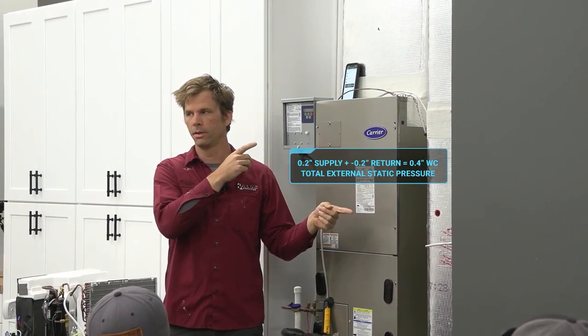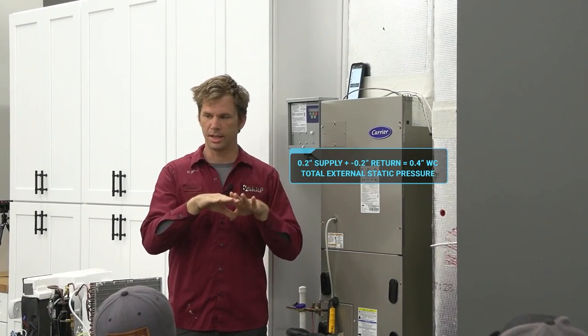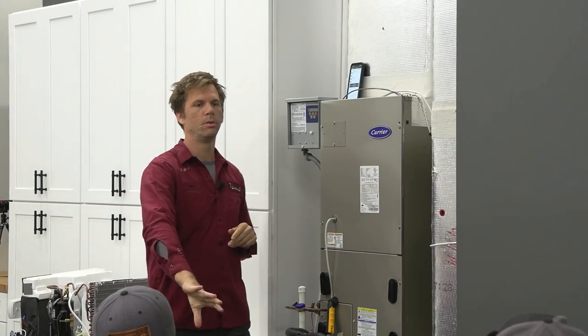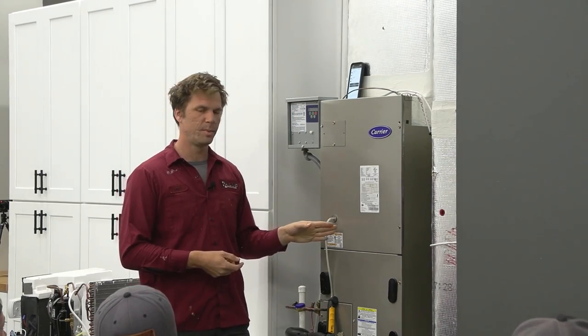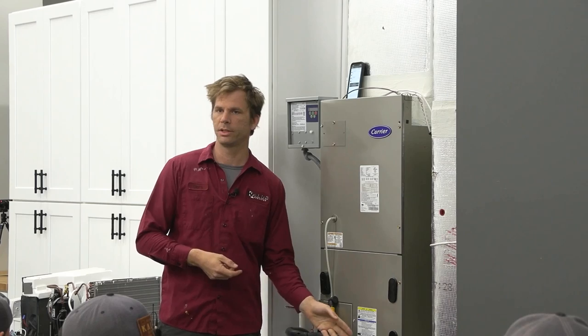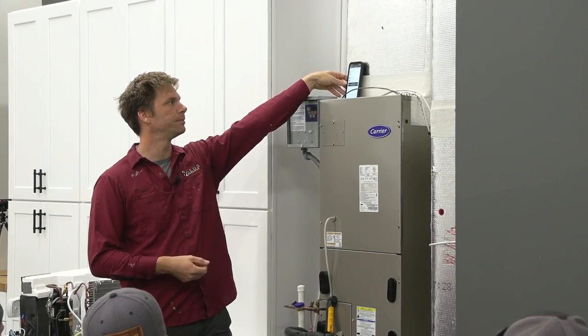We add them together. We have 0.4 as our total. We have 0.2 resisting on the bottom side, 0.2 resisting on the top. It's a little bit different here. If you look at your MeasureQuick, these are both negative pressures, and so the total external is going to be a little bit off. You just have to do the math yourself.